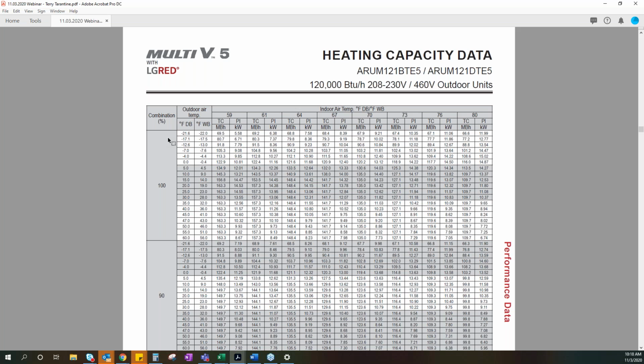We're accomplishing this through modulating compressors and a technology called flash injection. Basically, we're ramping the compressor up past 60 hertz, which normally drives a lot of heat into the compressor windings, and then we flash inject refrigerant. It absorbs the heat, and then we transfer that heat into the space when we're in heating mode. An incredibly efficient way to do this, very efficient.